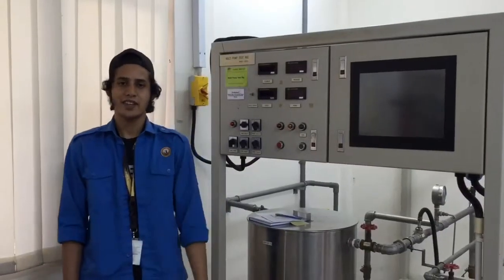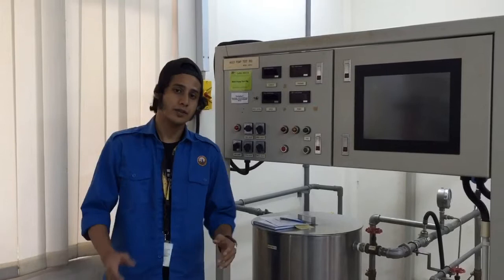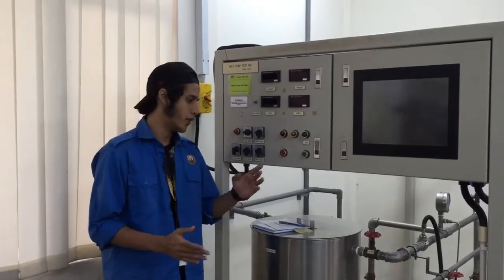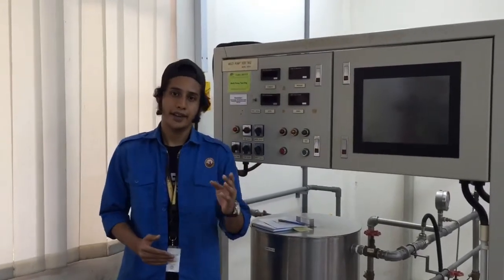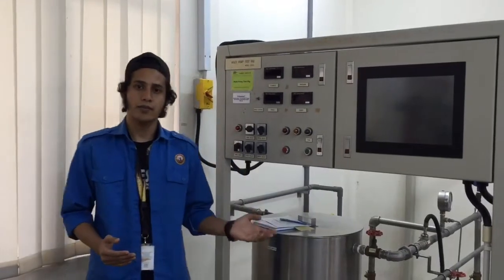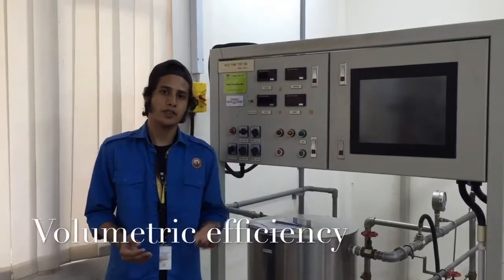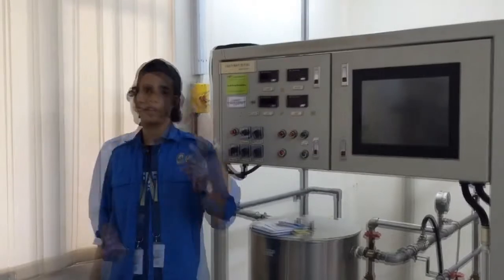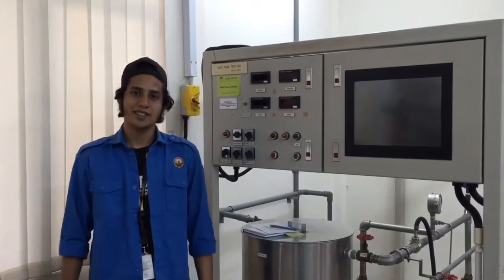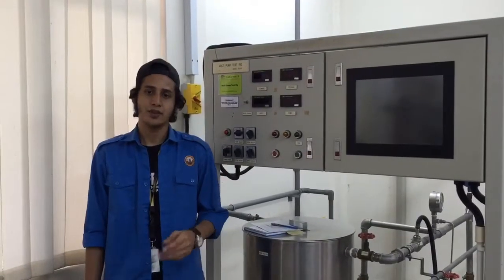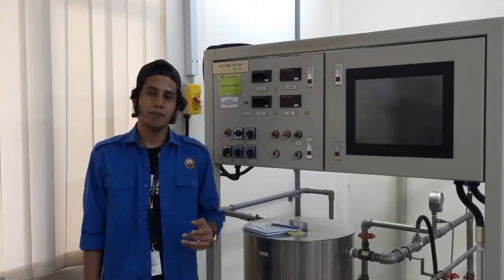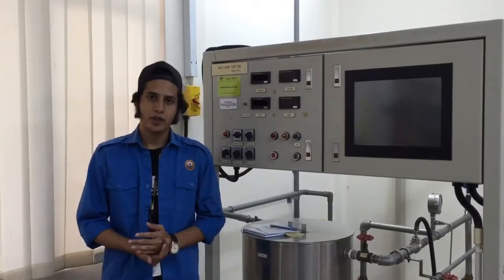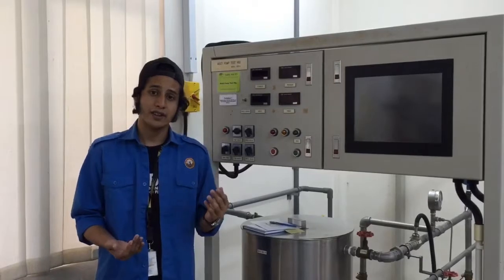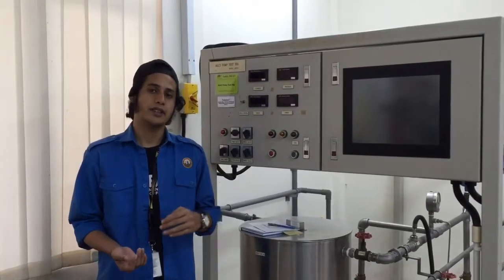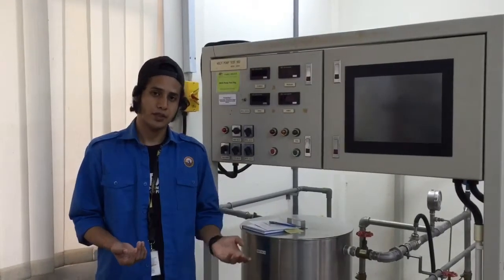Last but not least, the difference between the measurements taken for centrifugal and gear pump is that for the gear pump, we calculate the volumetric efficiency. Volumetric efficiency is the ratio between the actual flow delivered by the pump at a given pressure over the theoretical flow, which indicates the pump displacement over speed.